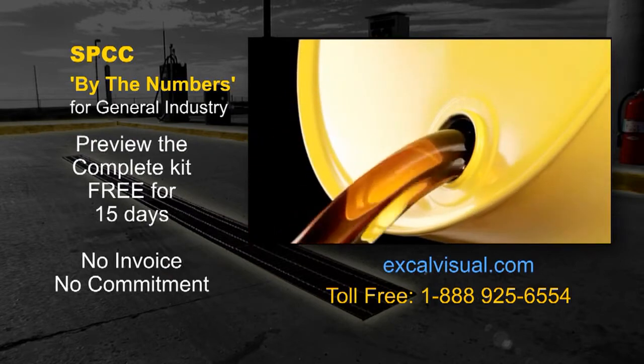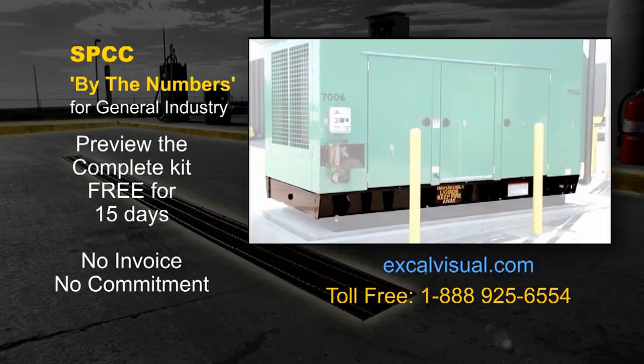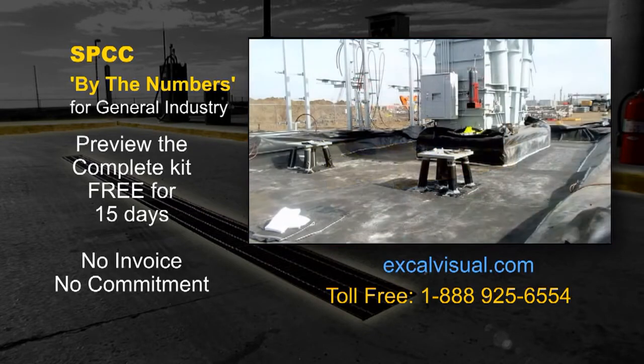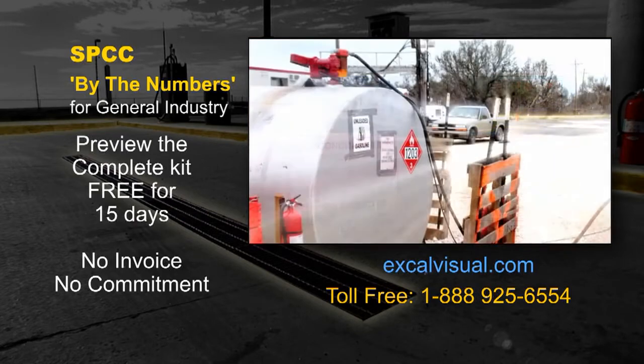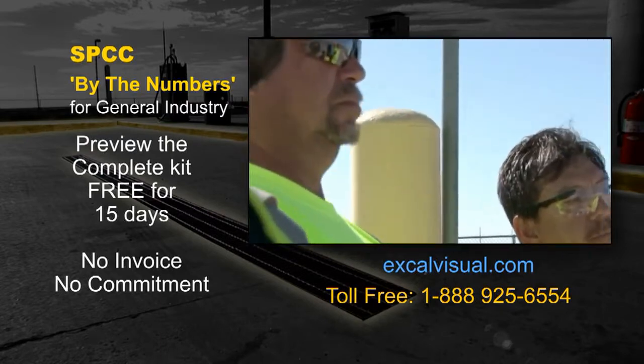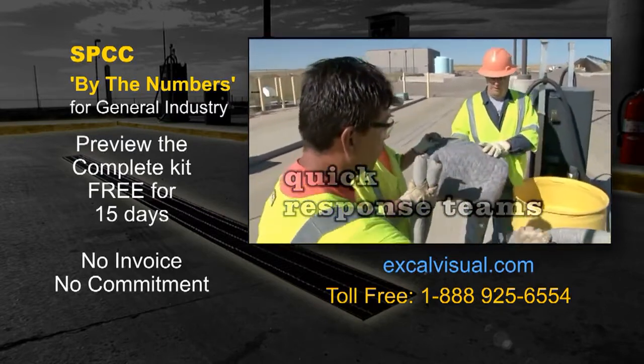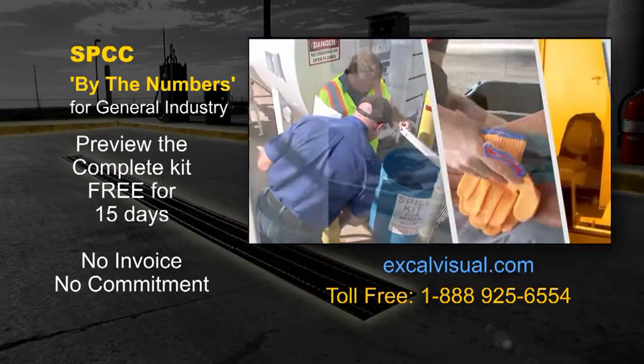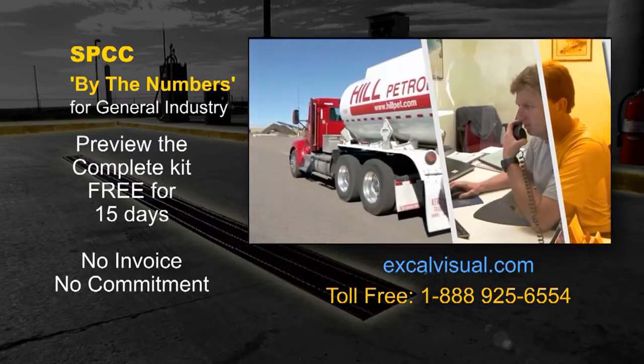Containments must be made of materials that are impervious to the tank's contents to hold the spill until it can be detected and cleaned up. Formed and sealed concrete, steel, plastic, and membrane-lined earthen berm basins can meet this requirement. In cases where secondary containment is not feasible, a team of employees should be trained in quick response techniques to deal with any oil mishap. These teams would be equipped with spill response and cleanup tools, and would be on call immediately when oil is being transferred or transported.